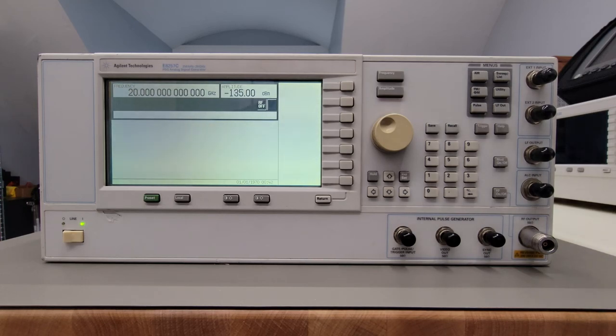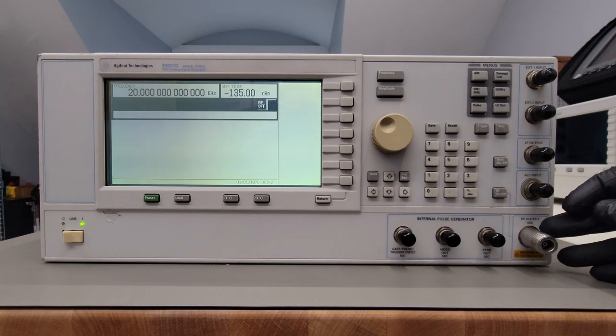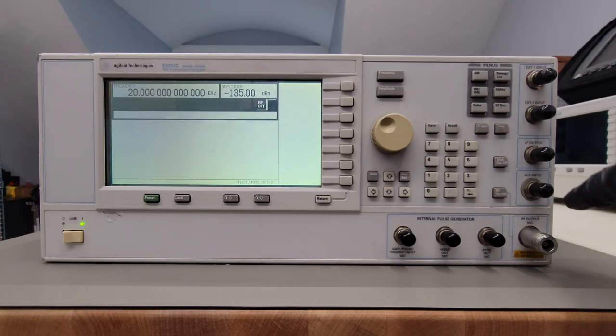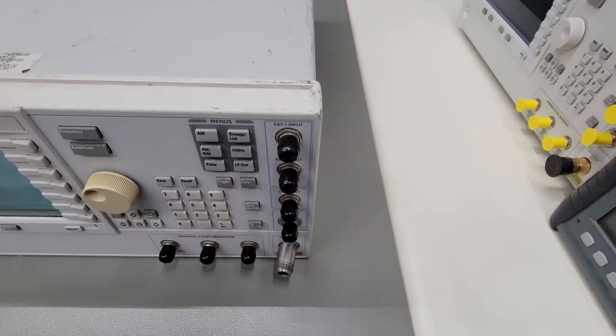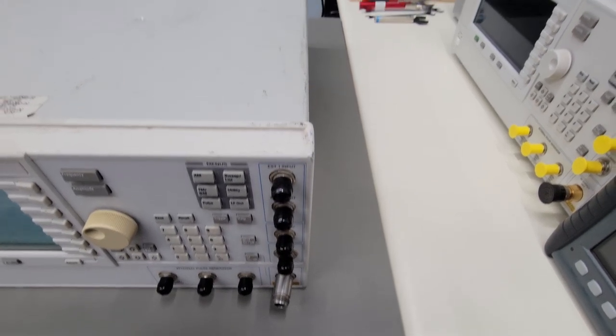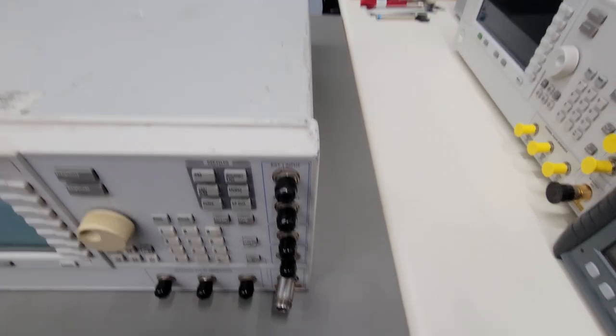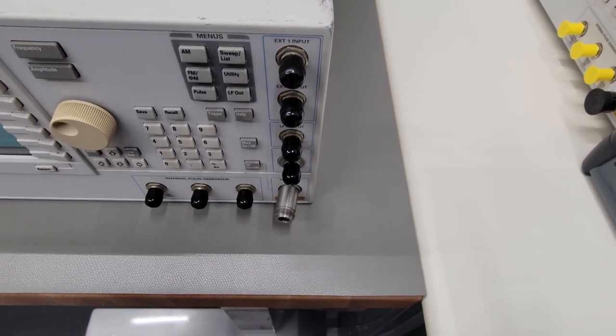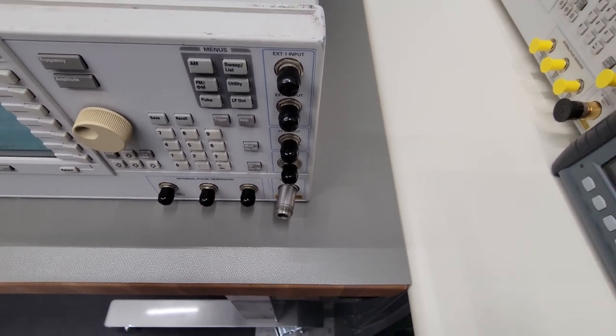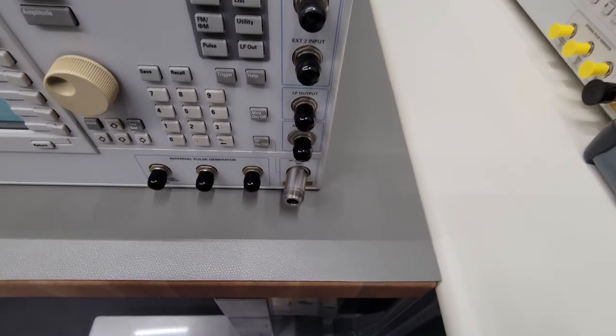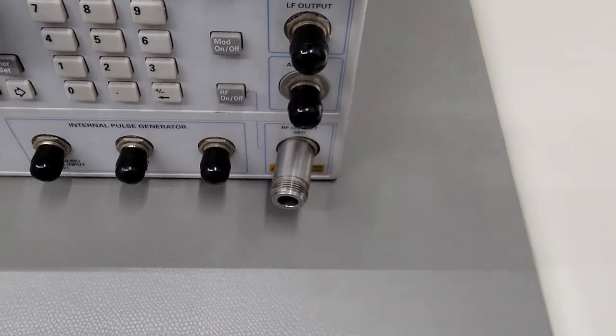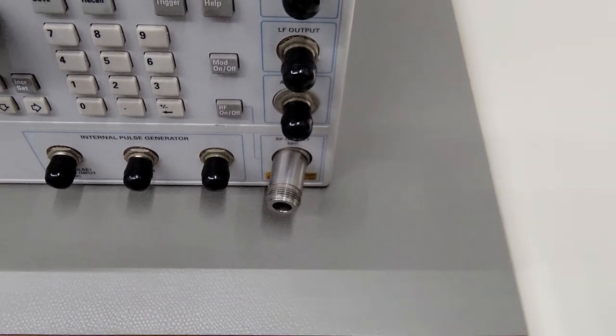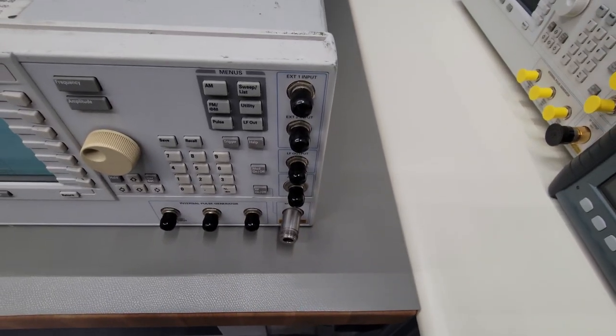I think the most concerning physical damage on this instrument is that the type N connector is actually bent quite severely. You can't see it from this angle, so let me reposition. All right, so you can see looking at the side of the unit here just how bent the front panel connector is. So we're going to have to make sure that none of the external threads on that type N are damaged, and then also clean that connector before we go ahead and mate anything to it.